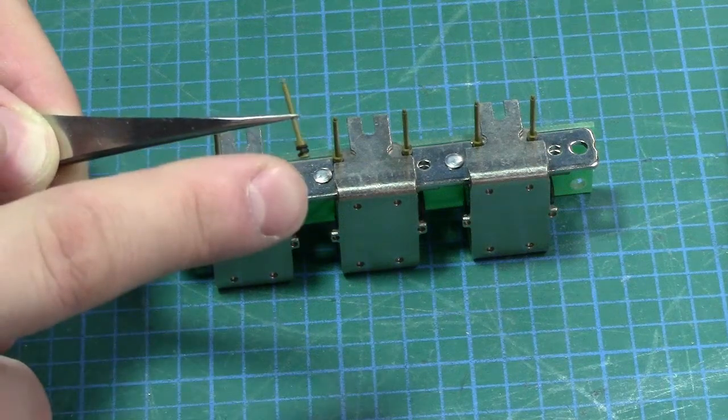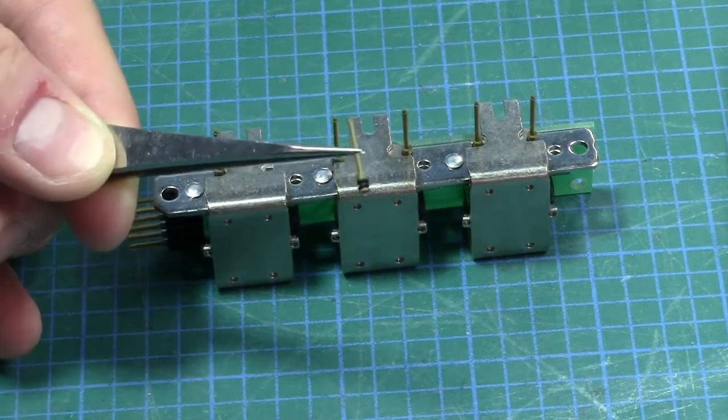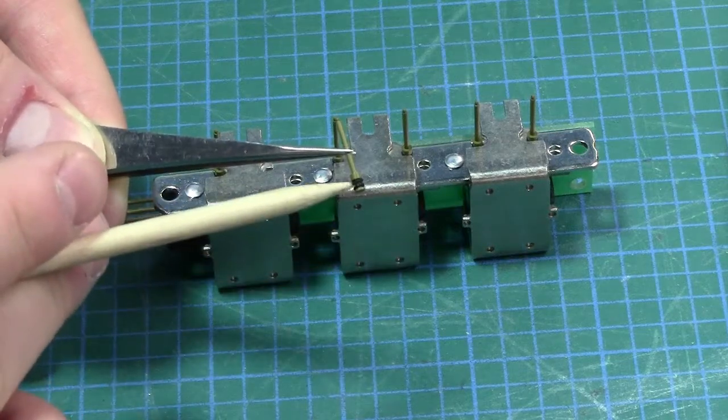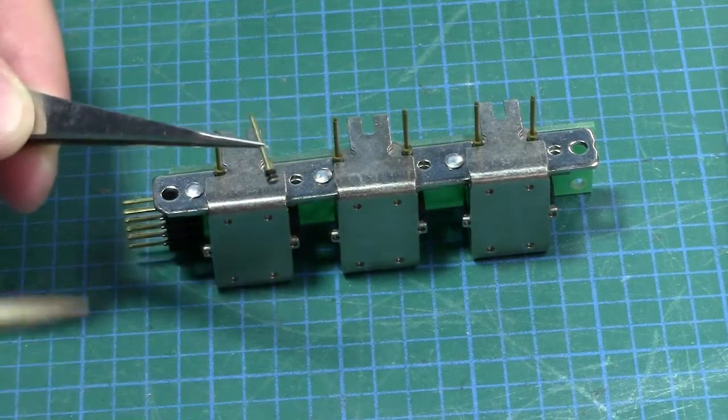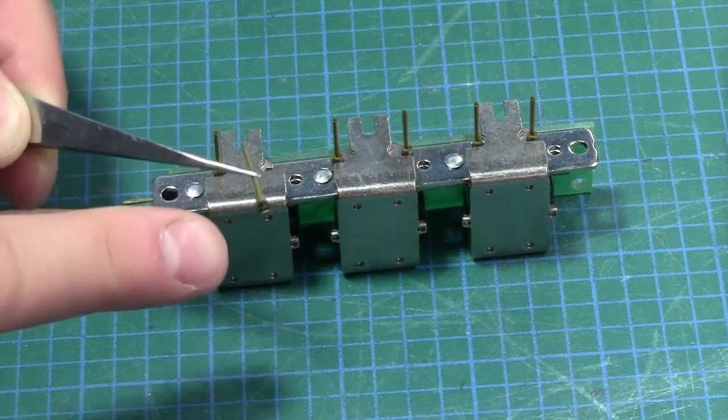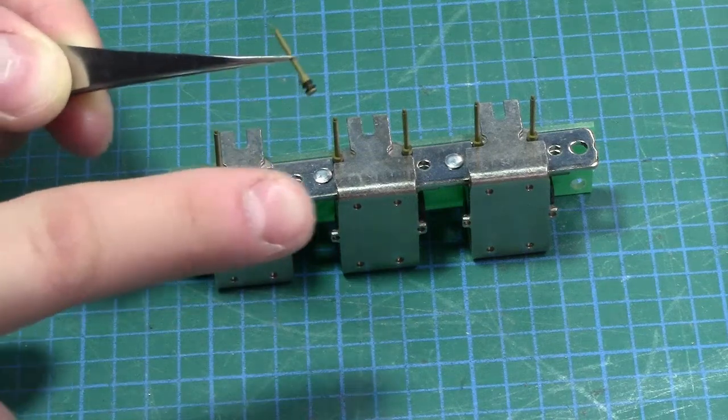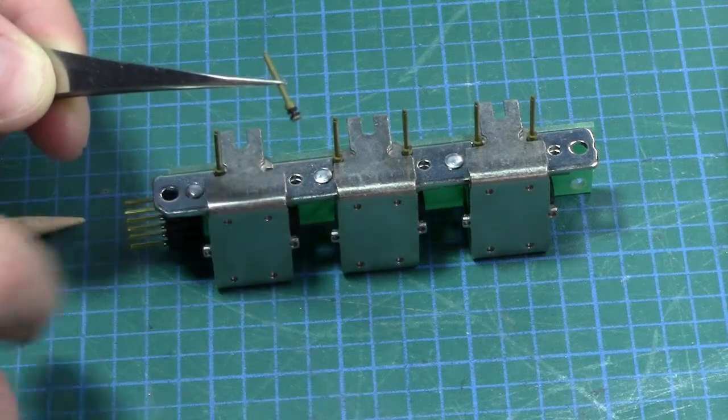And there's a small little separation between the two of them, and that is where that sort of that bracket goes in there. So these O-rings are the things that will dry out over time and potentially can cause you problems if they dry out and crack, or they can stick and do all sorts of nasty things. So these are the things that we're going to replace.